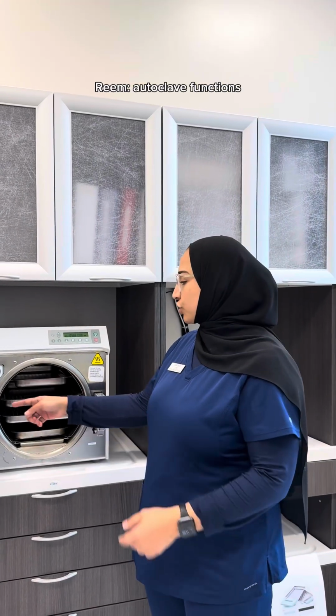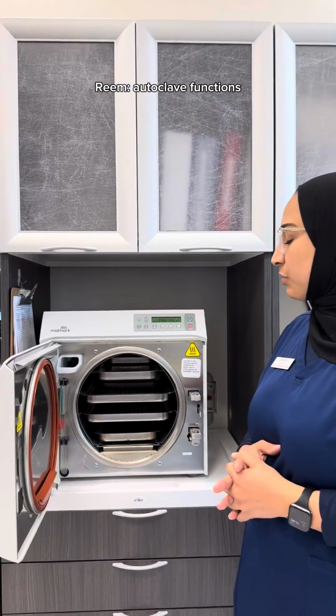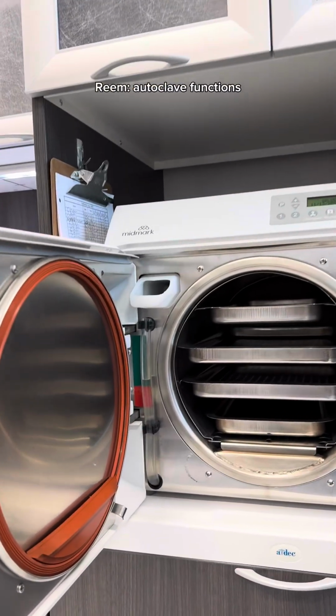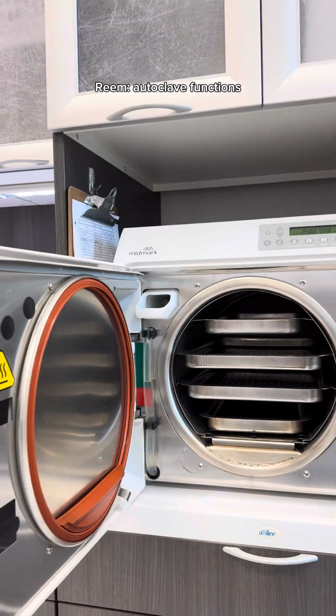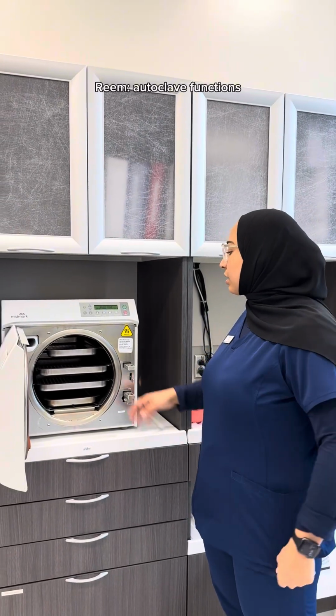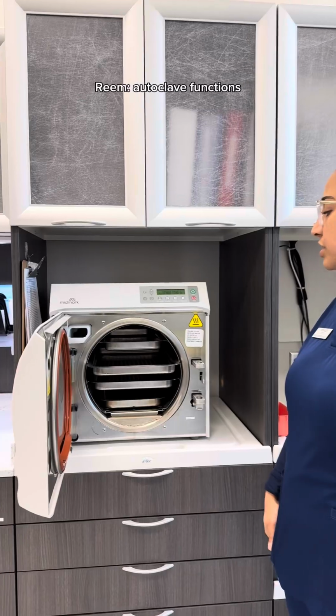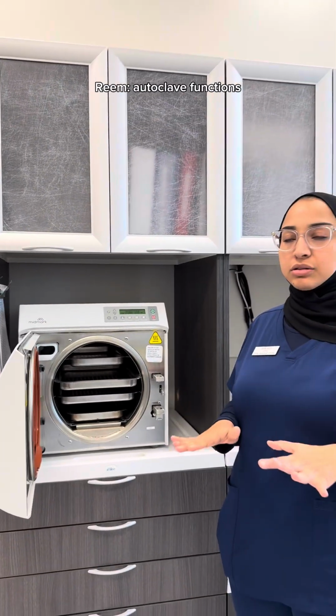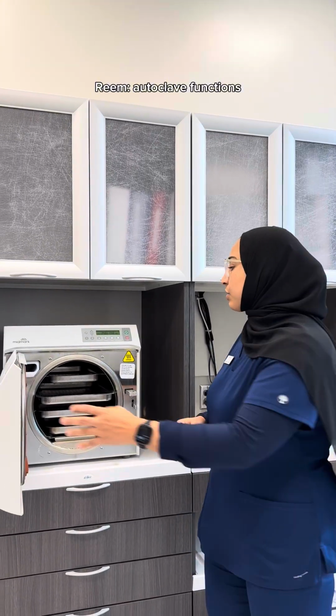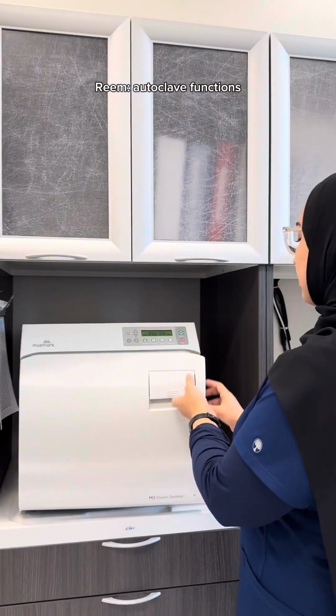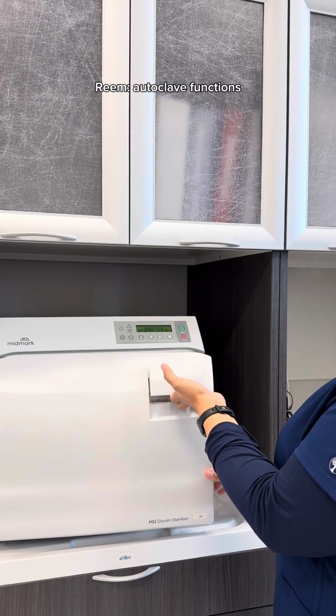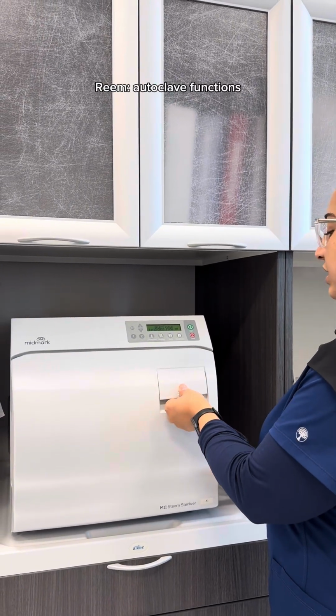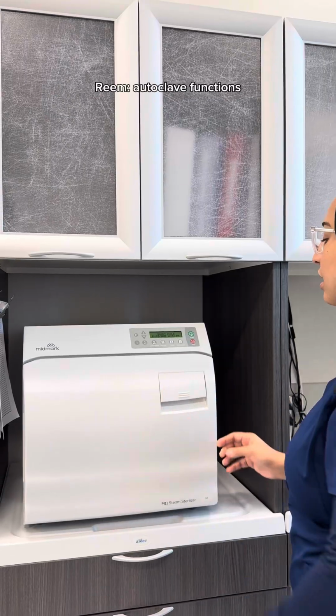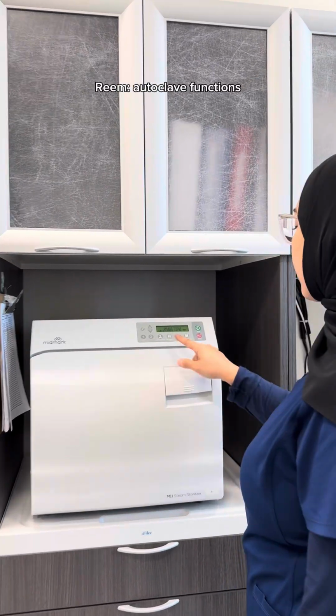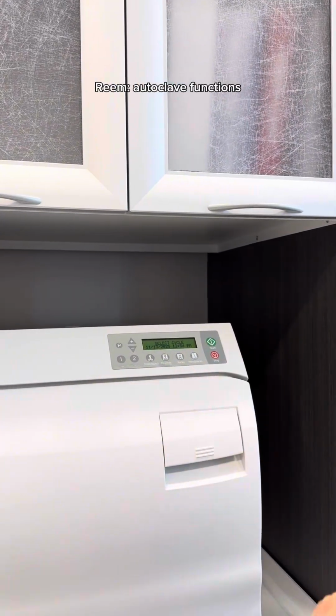After instrument processing comes the autoclave. First, we're going to have to make sure that the water level is in the green. If not, we will have to only refill it with distilled water. And then we will load the trays with the pouches, not crowded and not stacked next to each other, on the paper side of the pouches. And then we will close by leveling the handle, and then close, releasing the handle. Now it's locked. And then we will start the unit by pressing on pouches and then start.